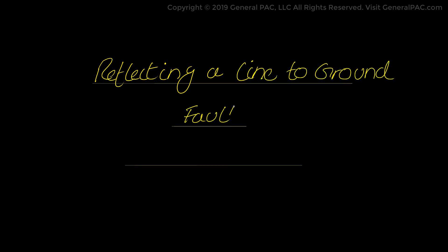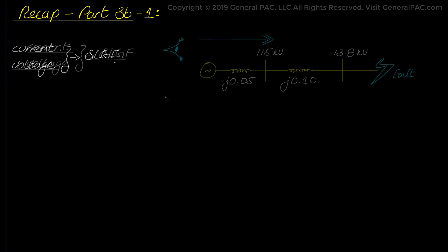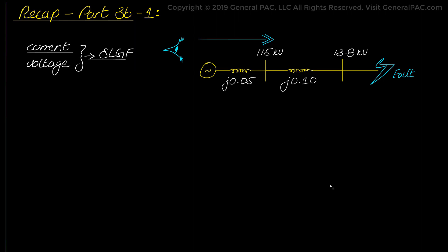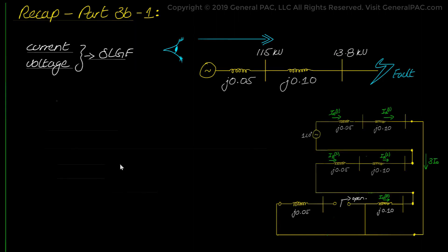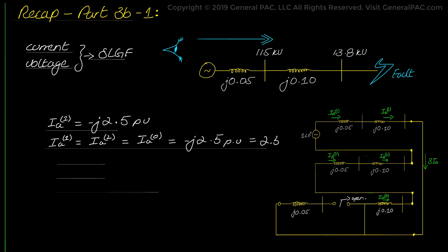Reflecting a line-to-ground fault on the high-voltage side. In this video we will see how we can reflect a line-to-ground fault current value which occurs on the low-voltage side of the transformer but reflected on the high-voltage side. Let's first have a recap of part 3b-1, in which we calculated the fault current and voltage values for a single line-to-ground fault that occurs on the 13.8 kV bus or the low-voltage side of the transformer. For a one-line-to-ground fault type, we found that the positive sequence current was equal to negative j2.5 per unit, and the positive sequence current equaled the negative sequence current which also equaled the zero sequence current, again at negative j2.5 per unit. That can be expressed as 2.5 angle negative 90 in polar form.